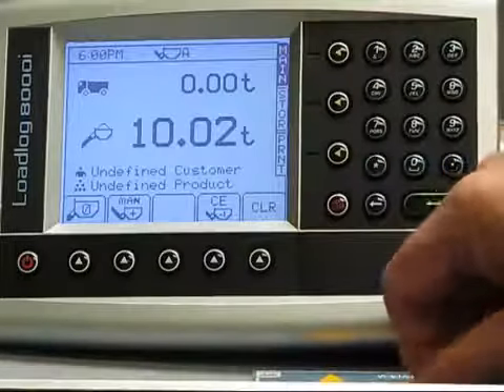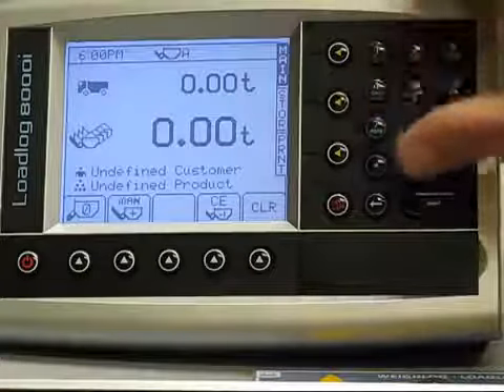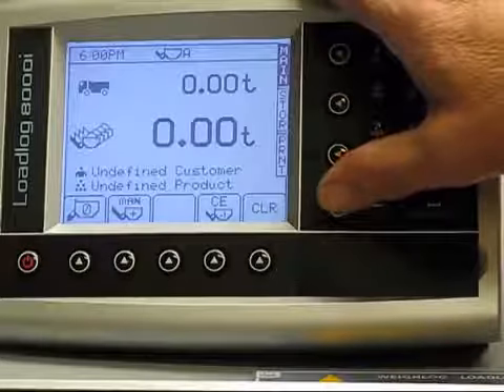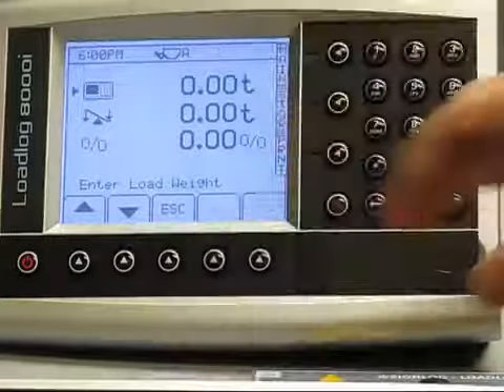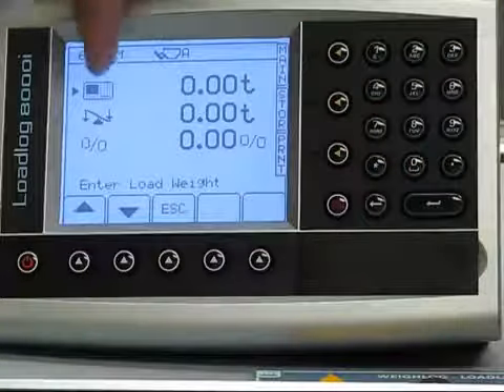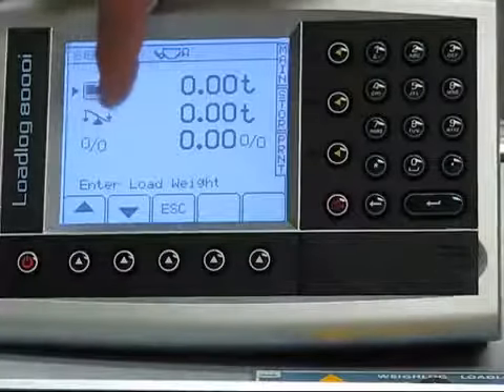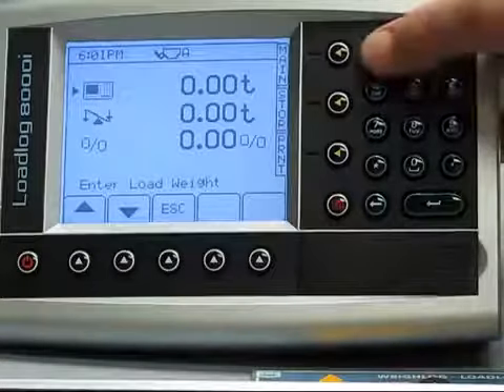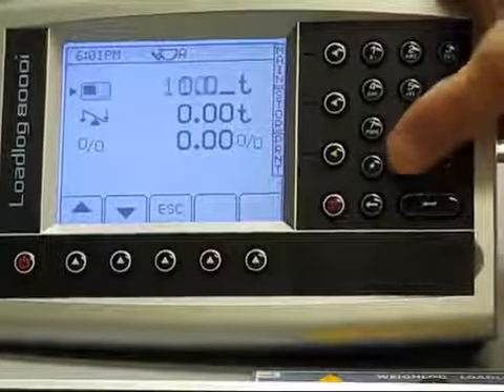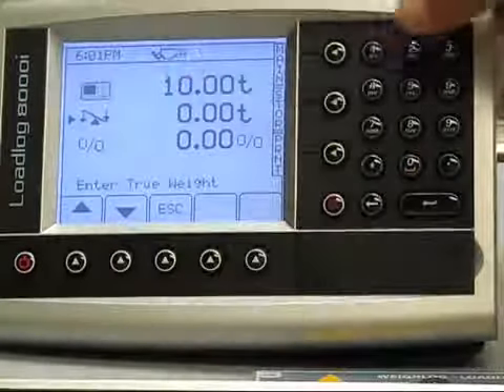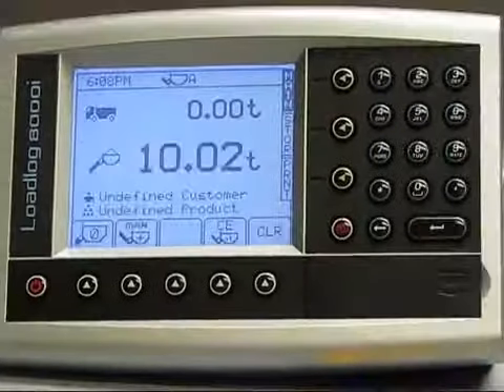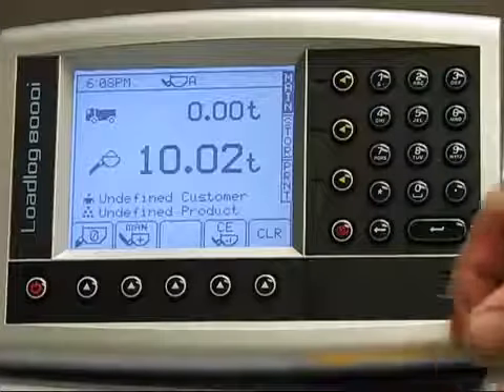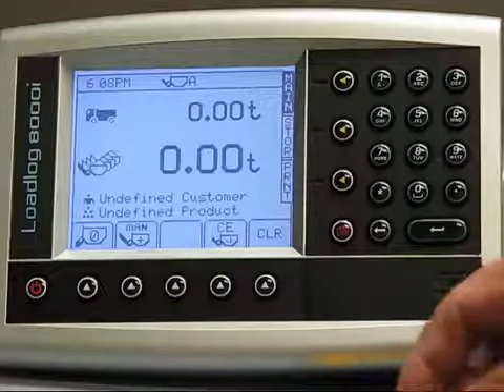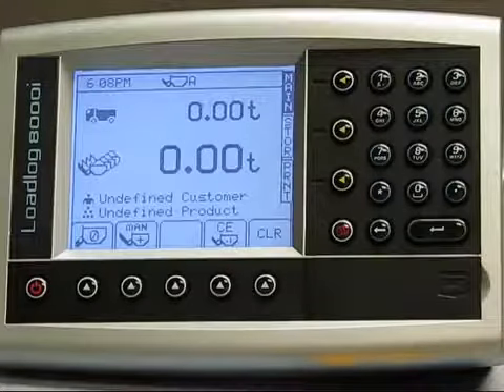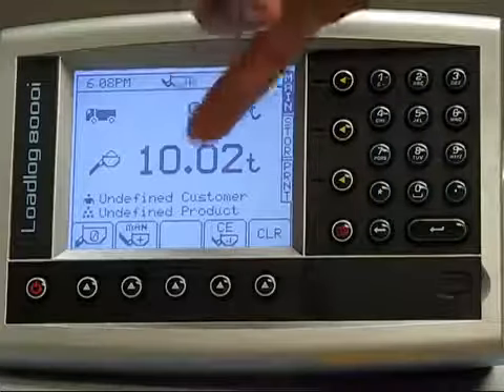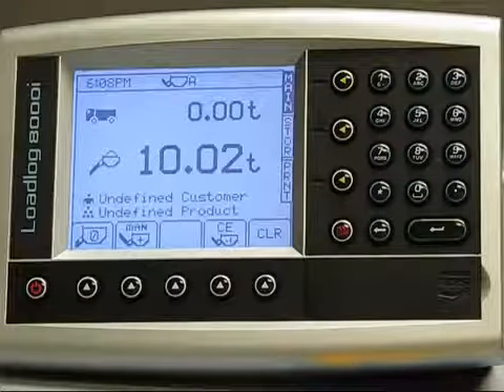Once you have this, if you need to adjust the scale, that's called nudging the scale. What you would do is press the menu key again and go to the nudge screen, where the upper line has the display, the 8000i, and the middle line is the actual scale. So if the display said it was 10, but it was actually 11.5. Once you have the scale calibrated where it repeats the weight of the full bucket, and in this case we're doing it in static, this is 10.02 tons, so it is repeating quite well.